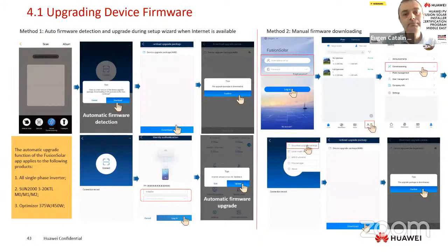Some troubleshooting. During the installation process and monitoring process and so on, we need to do different things. Upgrade, for example. In the residential field, in general, if you have the latest FusionSolar application, when you connect to the inverter, the update will be automatically generated by the application. The application will have the latest firmware. You connect to an inverter that has an older firmware, and the application will ask you to update the inverter, and you cannot skip this, so you need to continue with the update. The second one is to update from the web. Only the installer account has this access to update the inverter. So let's say this process is not so complicated, because the inverter will automatically ask for the update.